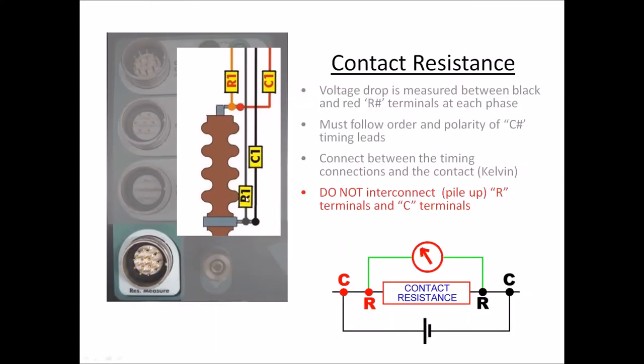This corresponds to the typical connections in a milliohmmeter — what we call the four-wire or four-terminal connection, also known as the Kelvin connection. In the Kelvin connection, you have a current injector generating current across the conductor, and then voltage drop terminals placed on both sides of the contact whose resistance you want to measure. You always place the voltage drop measuring terminals as close as possible to the measured spot, and the current injection spots can be placed wherever you wish.